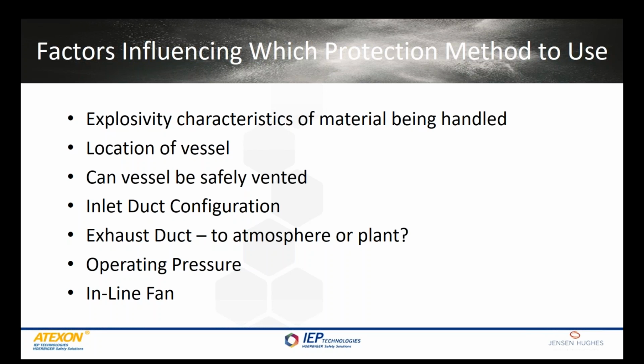Location of vessel is going to have a big impact, obviously, to determine whether or not your vessel can be safely vented to the outside. The inlet duct configuration is going to help tell us whether or not a flap valve will work, or whether we need to use a chemical barrier to stop flame propagation. The exhaust duct: in some cases, especially in the northern climates, the exhaust from, say, dust collectors is to go back into the facility for energy conservation. If that happens, then we have some other things to consider.